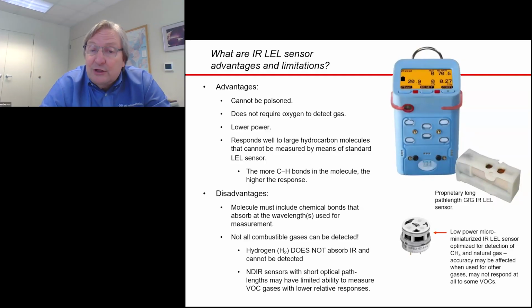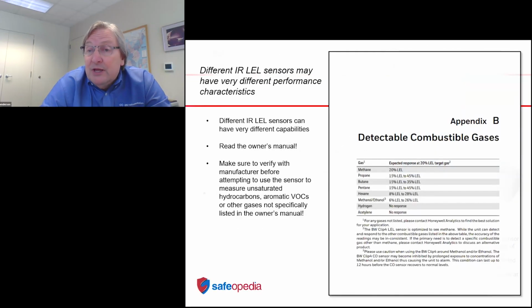That's how you're measuring the molecules. You're shining a beam of infrared light through a sensing chamber, and you're looking for absorbance. And hydrogen does not absorb infrared light. That's why you can't measure hydrogen at all. And acetylene can absorb infrared light, but not at the wavelength that you use in portable instruments. So with a portable instrument IR LEL sensor, acetylene is also invisible, which means you're going to need to measure it with a different type of sensor, like an electrochemical sensor.